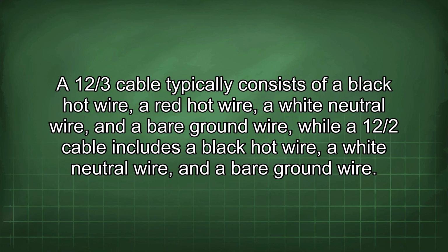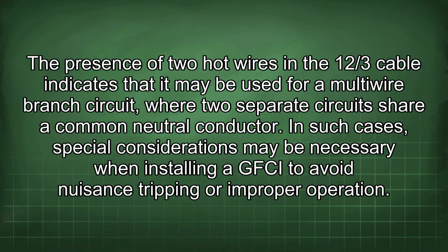The presence of two hot wires in the 12/3 cable indicates that it may be used for a multi-wire branch circuit, where two separate circuits share a common neutral conductor. In such cases, special considerations may be necessary when installing a GFCI to avoid nuisance tripping or improper operation.